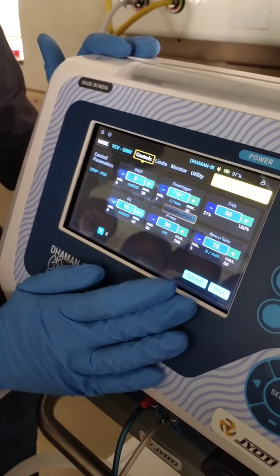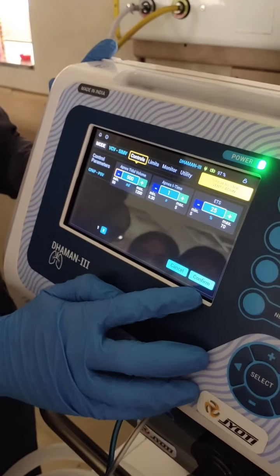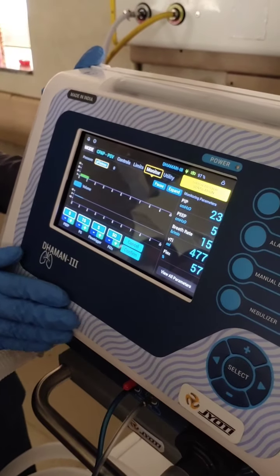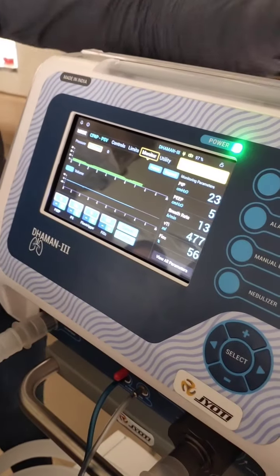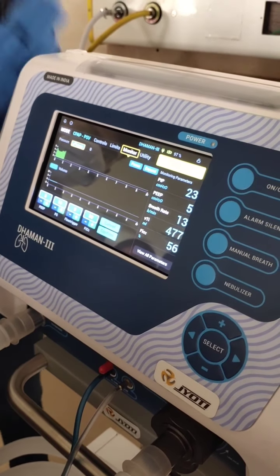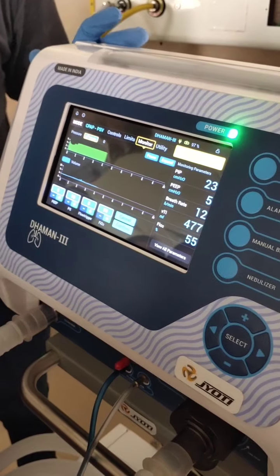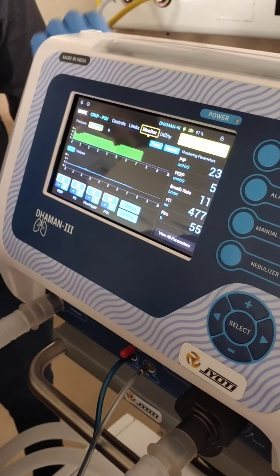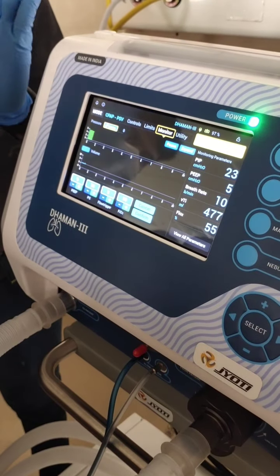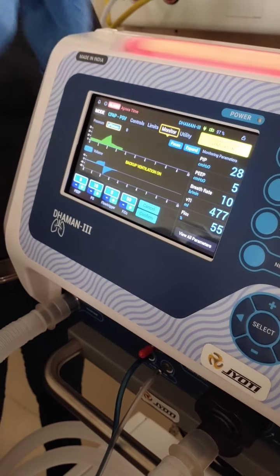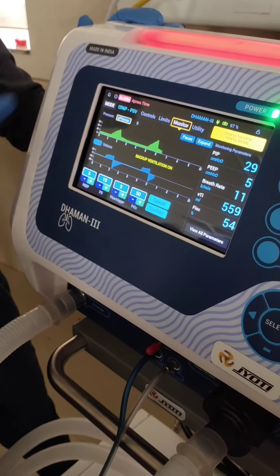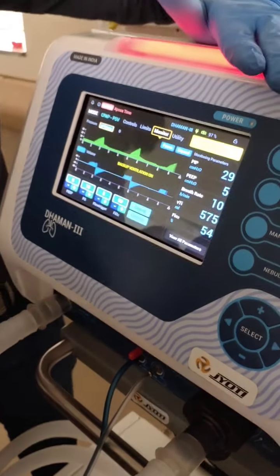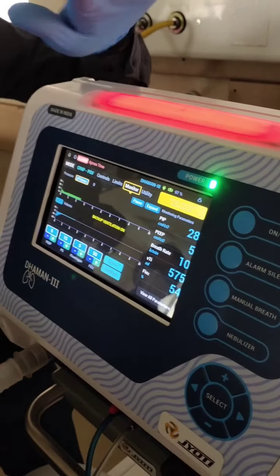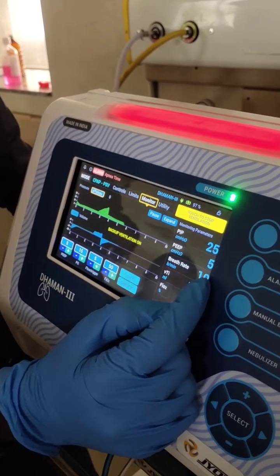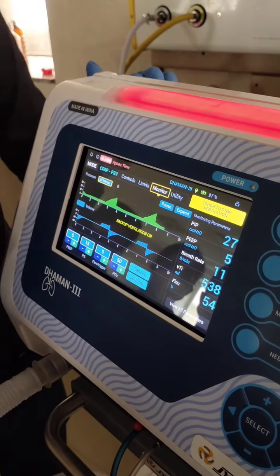So go to the CPAP and next. So I kept the default values. So next. So I confirm. Yes. So for the CPAP settings, how it's going. Okay, once it is stabilized, there will be an error. We all know the apnea time error will be there. So whenever the patient's spontaneous inspiration comes, then the error will come after 50 seconds. Within the 50 seconds, we have to reduce it. Depending upon the patient, we have to reduce it. Okay. So here it is coming now. So the apnea time. At first, in the initial time, an excessive leak error will be there. Once it is stabilized for the breathing rate, that error will be reduced. So now the apnea time will be there.